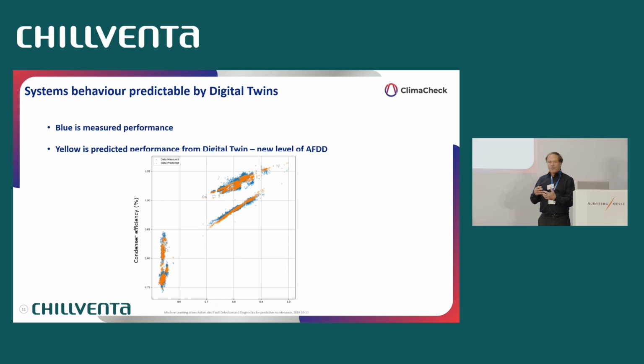So this is just showing condenser efficiency, where we have trained it on one system and we are applying it on another. We don't need to have data for each system and train on to be able to set it up. Because, I mean, the condenser is the same on many others. We don't even need to have exactly the same condenser, because this happens to be a plate heat exchanger, so we cannot use a plate heat exchanger model for a tube and shell or an air condenser. So we need to, again, use a similar type, but a plate heat exchanger condenser will behave fairly similarly if it's a 10 kilowatt, 100 kilowatt, or megawatt system. The physical procedure is the same, so it works even much better than I hoped.